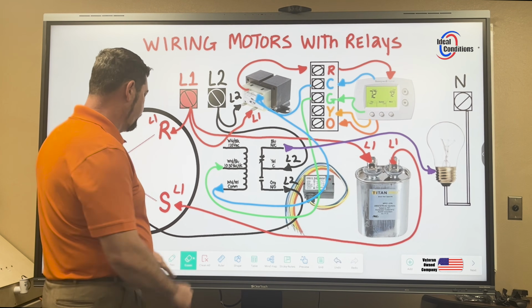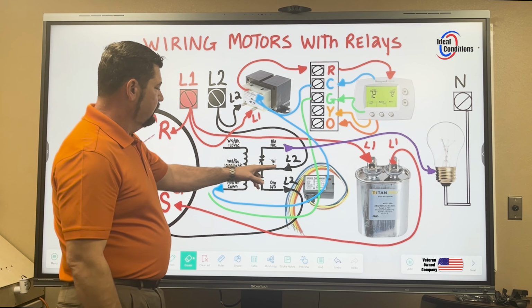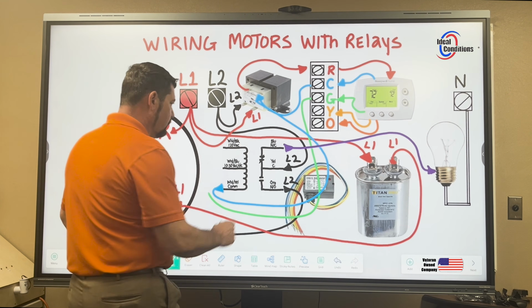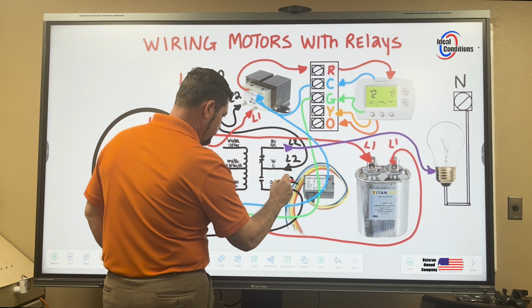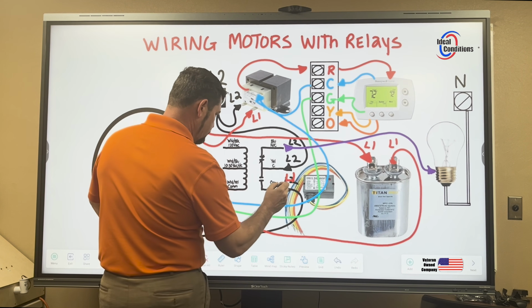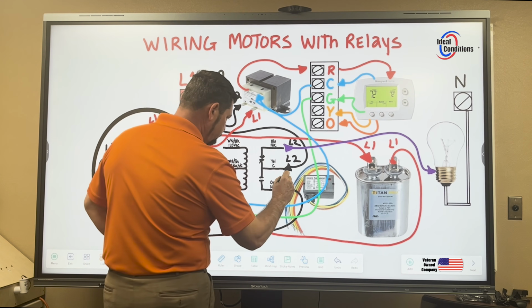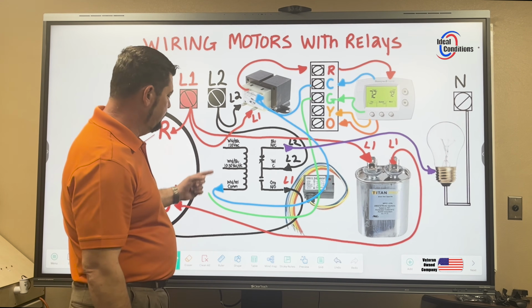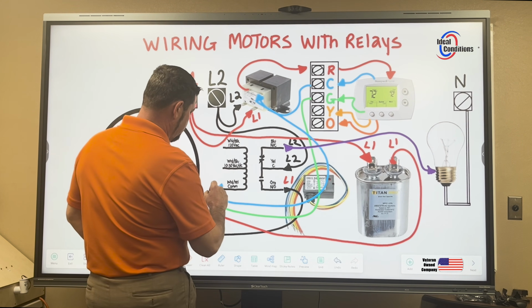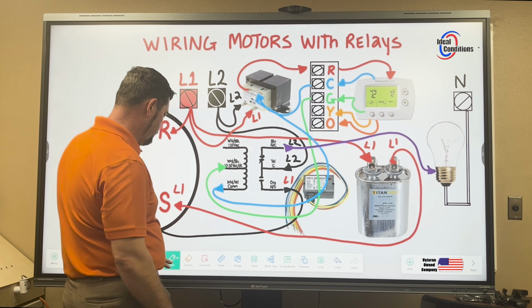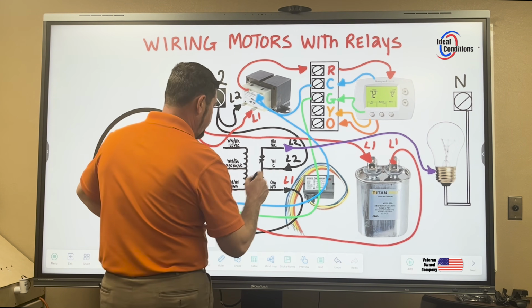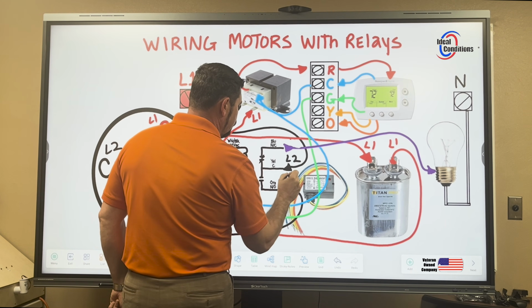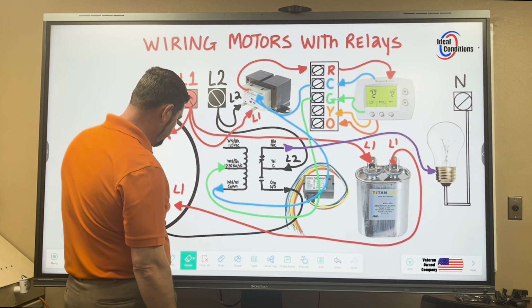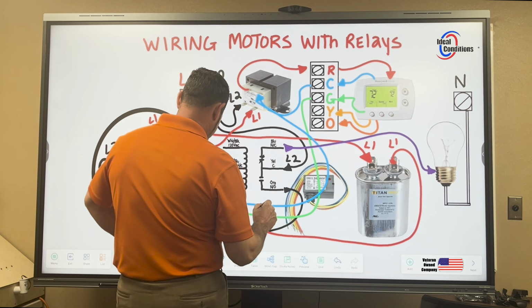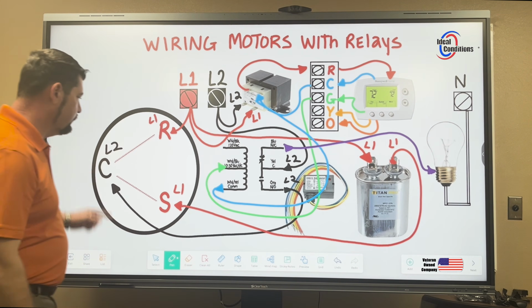And so if I lose 24 volts here, then L2 will be now present here, and, excuse me, L1 will be present here. When I get 24 volts there, when I have my 24 volts input here, then all that changes and I don't have L2 present here anymore. Where I have L2 present is now here. And so L2 will be here, the motor will run.